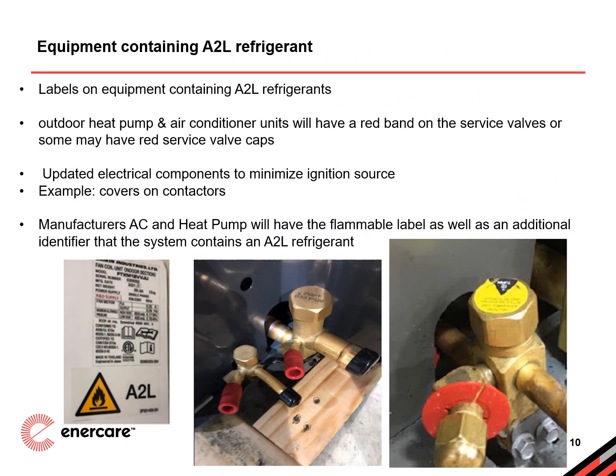Some of the key updates and requirements when working with equipment containing A2Ls. First, all equipment that uses A2L refrigerants will feature clear and visible labels. These labels ensure that anyone interacting with the system is immediately aware of the refrigerant type and its associated properties, such as its mild flammability. Second, outdoor heat pump and air conditioning units will have a red band on their service valves, or in some cases, red service valve caps. Like 410A before it, this serves as a visual identifier, making it easy to differentiate these systems from those using more traditional refrigerants.